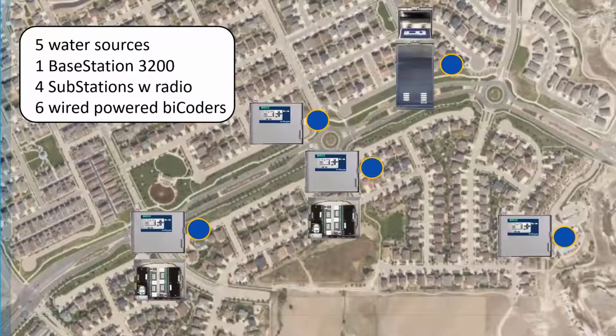And just for repetition, these are all search and assign devices. At that controller, turn the dial to assign. When you click search and assign, it goes out wirelessly and brings back into the controller all the different devices that may be connected to those substations - flow sensors, pressure sensors, decoders. All the two-wire devices are search-and-assignable in that wireless fashion.